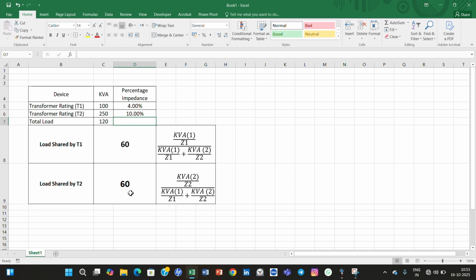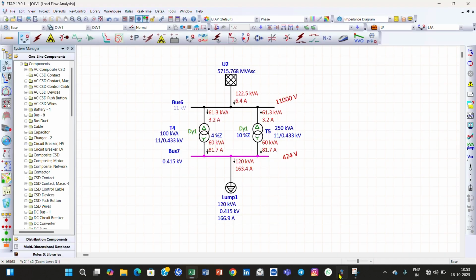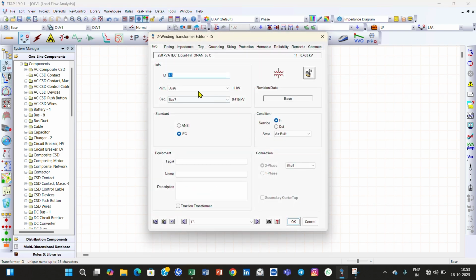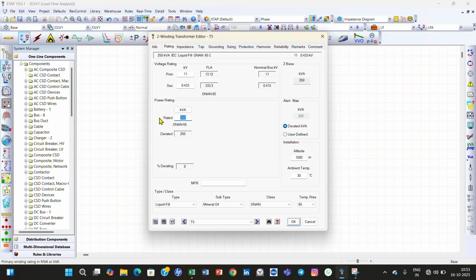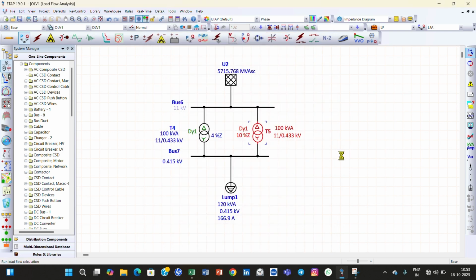Now we will do one more thing: we change the transformer rating here and keep a change in the percentage impedance from 4 to 10%. Now you can see the load shared by the first one is 85.7 and by the second one is 34.3. That is totally reversed compared to the first case. Now we change this transformer rating to 100 kVA and see what load is shared by the transformers. It is 85.7 and 34.3.